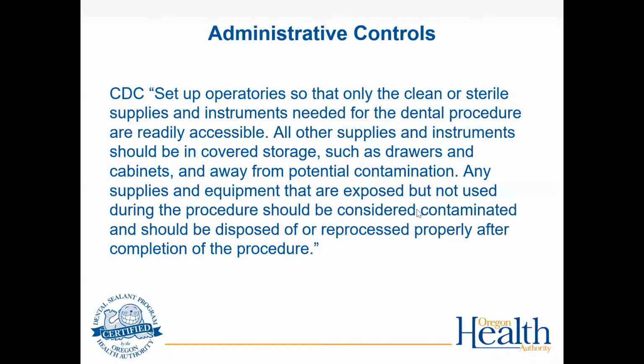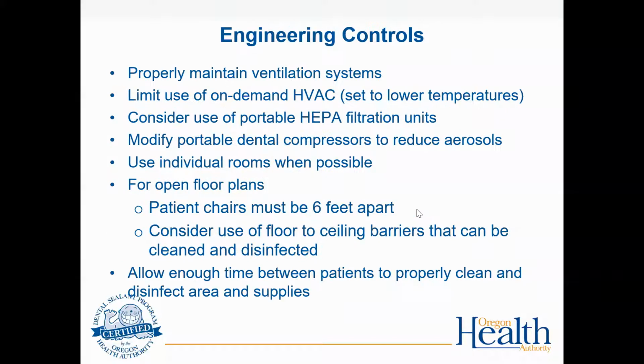And a direct quote from CDC about that. Engineering controls include things like properly maintaining ventilation systems. That's not something that we have control over in the schools. And consider using HEPA filters. The Dental Works units are finishing up developing a ULPA filtration system that's a box outside of the compressor, and that apparently filters even more than a HEPA filter. So modify your portable dental compressors.